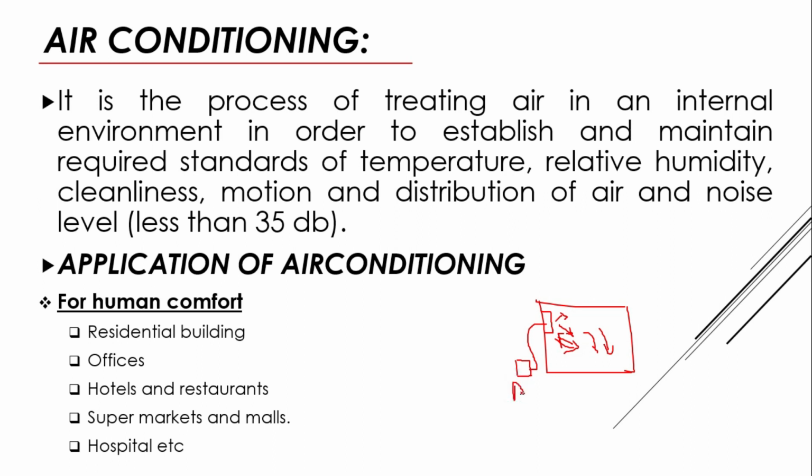This is the AC, and we are maintaining the temperature here at 76 degrees Fahrenheit, and relative humidity should be 30 to 60%. This is what we are maintaining with the help of air conditioning, and the noise level should be less than 35 decibels. Decibel is nothing but the unit of sound.